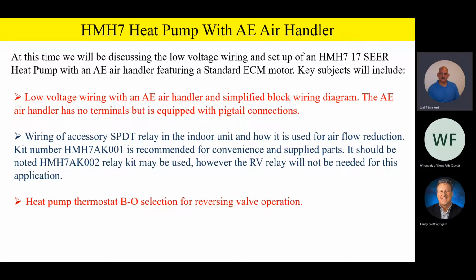Now, it should be noted also that whatever heat pump thermostat you select is going to have to be a thermostat that has a BO selection for reversing valve operation, because we're going to energize the reversing valve in the heating mode on this product. Unlike the rest of our Champion heat pump product, this one energizes the reversing valve in the heating mode compared to the O terminal in the cooling mode like we have on the other product. It's not bad, it's just different. And we just want to make sure everybody understands that.